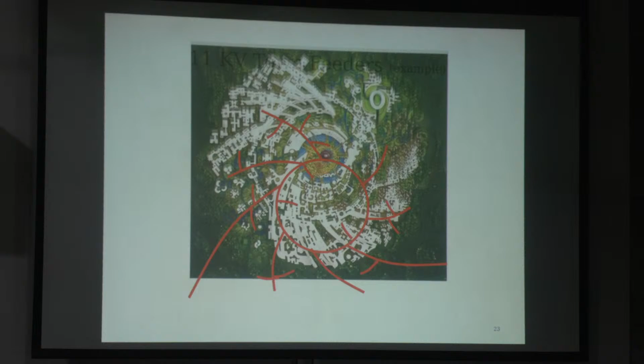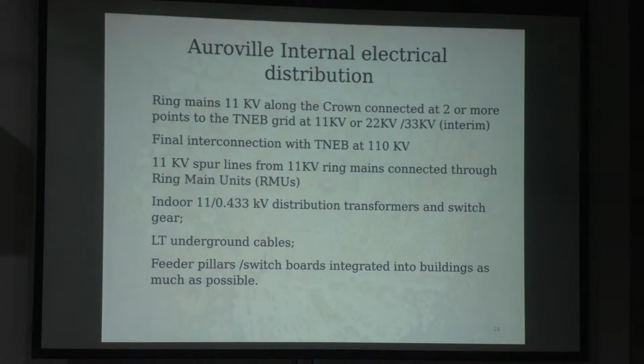Now maybe this is basically the summary. So 2 connections to the outside world. Finally, an interconnection at 110 kV level when we cross a certain population. Transformers are all indoor, LT underground cables, so no more overhead lines, all gone. Energy efficient systems, because of this design, we get a very low I²R losses. The grid is fed from Auroville grid-connected renewable energy systems, as I explained in the earlier presentation. They can export to each other and import from each other, the buildings and the clusters. All the meters that electrical service installs are all bidirectional meters, for those who know what a bidirectional meter is.